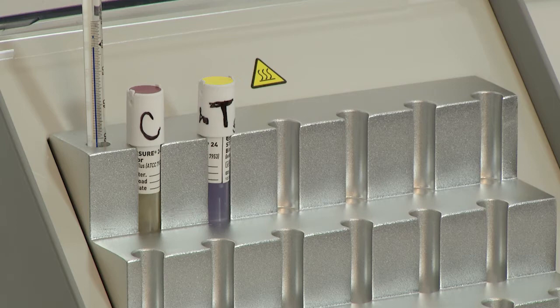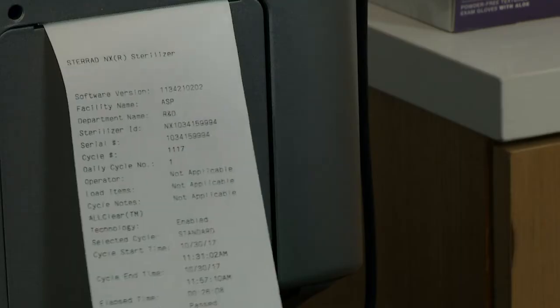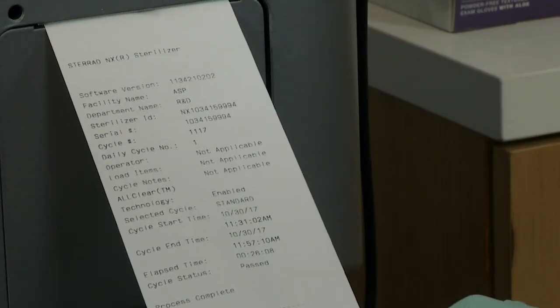If the processed BI changes color from purple to yellow, as in the positive control vial, and/or it exhibits turbidity, this indicates that conditions necessary to achieve sterilization in the STERRAD sterilizer have not been met. In addition to the BI, inspect the chemical indicator response for the correct color change and verify the cycle completion report shows cycle status passed and process complete.